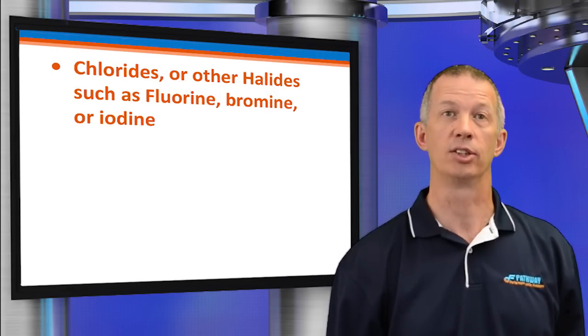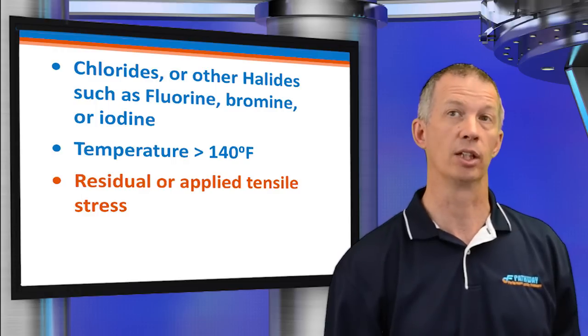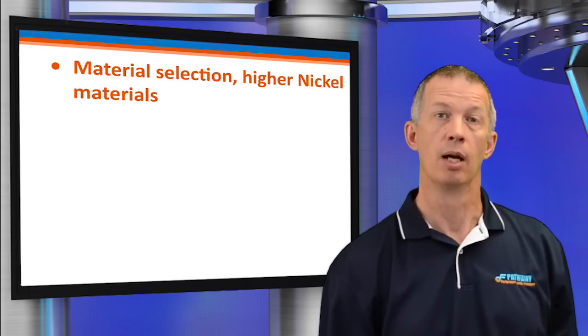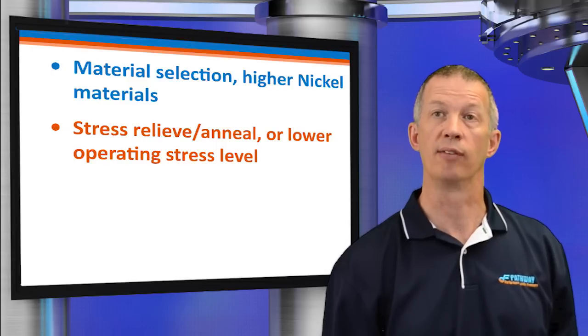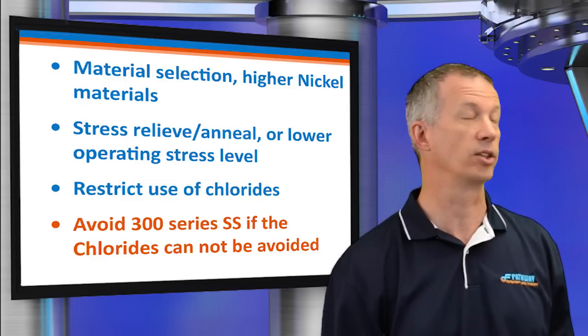What about chloride SCC or stress corrosion cracking? What would a user expect to find? Widespread branching cracks, typically at the convolution crest and usually across the grains. Conditions that cause chloride SCC include chlorides or other halides such as fluorine, bromine, or iodine; temperature greater than 140 degrees; residual or applied tensile stress; and an electrolyte such as water or steam. Solutions include material selection with higher nickel materials, stress relieve or anneal the bellows, lower the operating stress level, restrict the use of chlorides, and avoid 300 series stainless steels if chlorides can't be avoided.